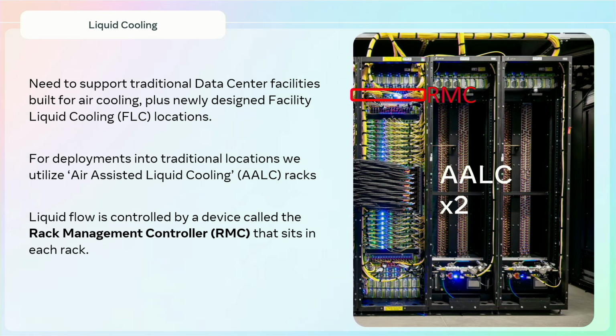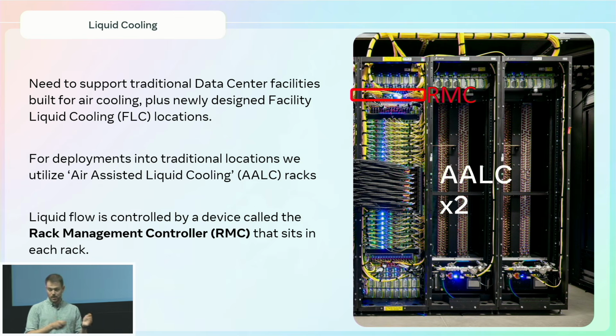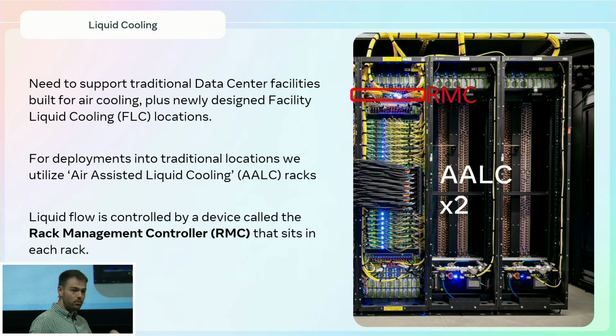On the liquid cooling front, like I mentioned, we support both traditional air-cooled facilities through the use of the AALCs. We also support newer buildings that have facility liquid cooling, which let you run liquid straight to the rack. In that case, during a deployment you'd see only the two middle IT racks, not the AALCs on each side, so a pod is now only two racks instead of six.